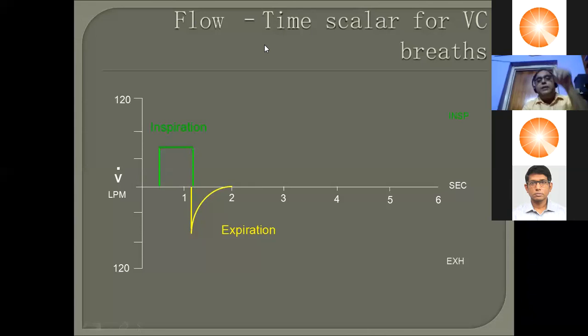I have not talked about the expiratory flow previously, but it's important to know this, because whatever your mode is, your expiration is always passive. So the expiratory flow is always the same whether you are in PC or VC, and it is again a decelerating flow. But let's come back to VC. The most important point here is that in VC, the flow time scalar is a square wave scalar, just like the pressure time scalar of a PC breath. So in VC, the flow time scalar is a square wave. Next, please.